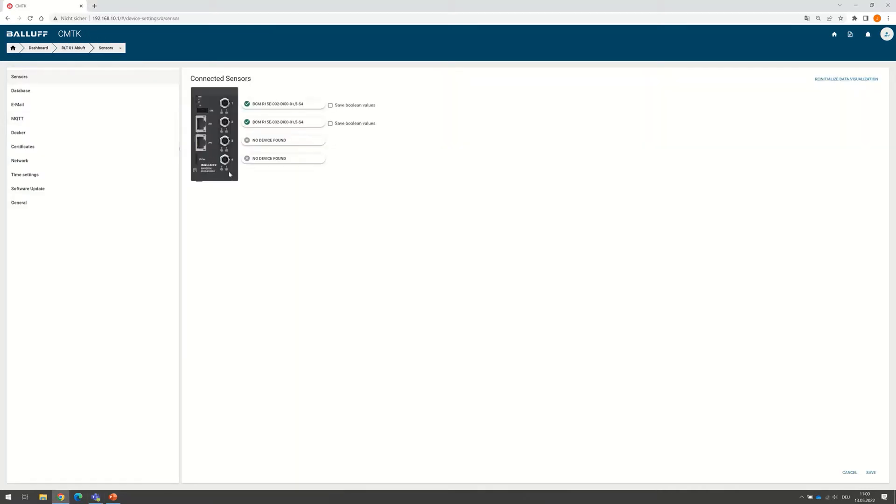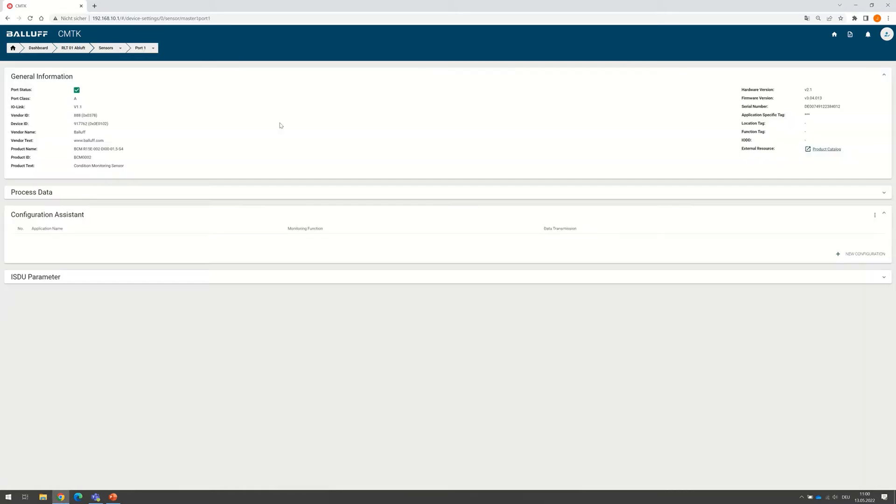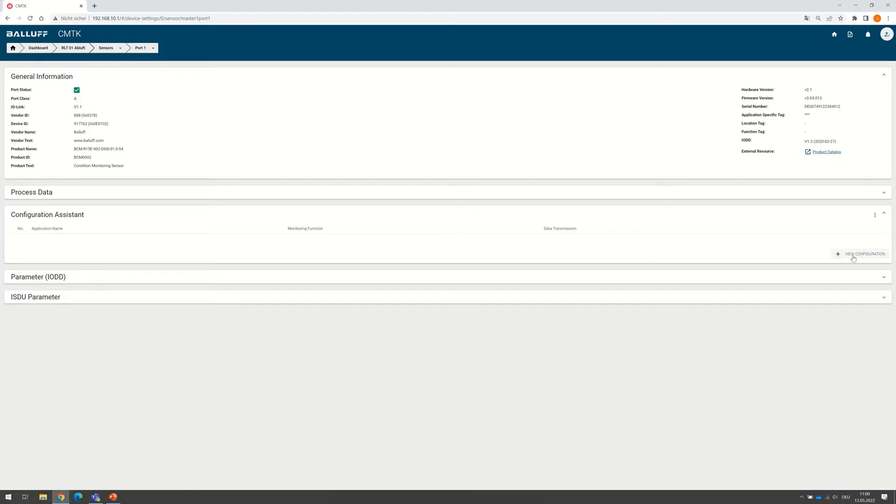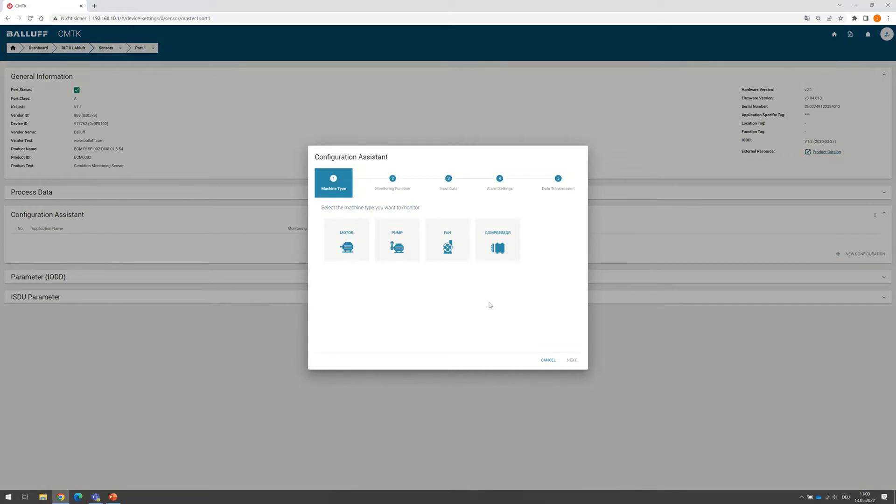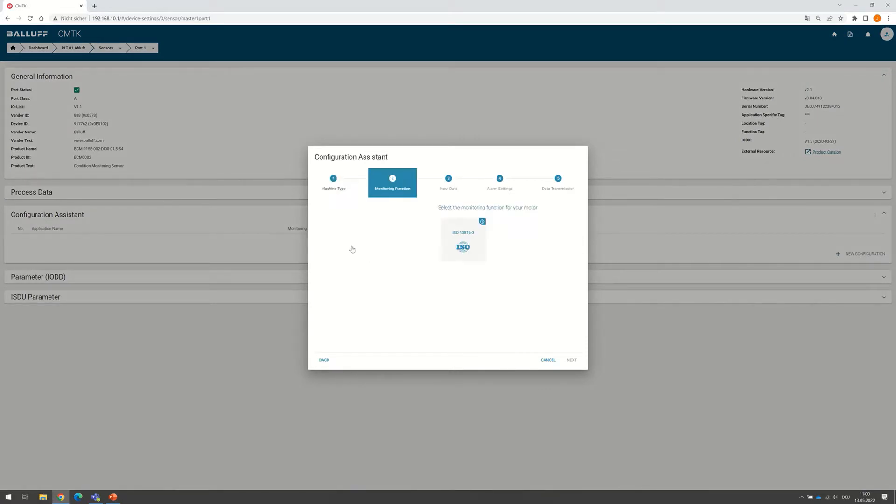Starting from the landing point, we click on the three points at the top right corner and click on setting to see the connected sensors. We choose the first BCM and see that we can add in the tab Configuration Assistant in the bottom right corner a new configuration. Since the first BCM is mounted on the motor, we choose motor.